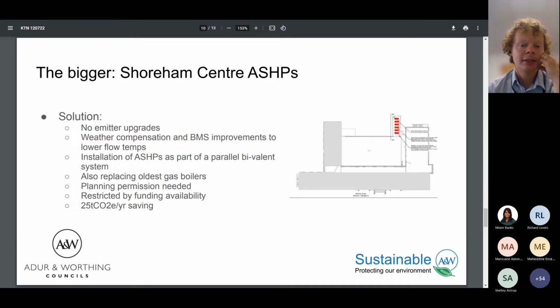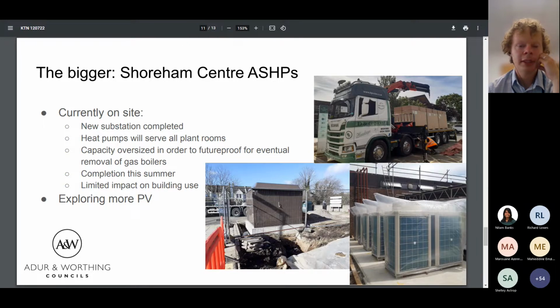We've had external design support for this project, which has been an interesting experience in itself. We've eventually agreed on a solution to install weather compensation and BMS upgrades, as well as new plant, which acts as a parallel bivalent system. This means the new system will run predominantly off air source heat pumps, with the gas boilers only firing when external temperatures fall below a certain point.